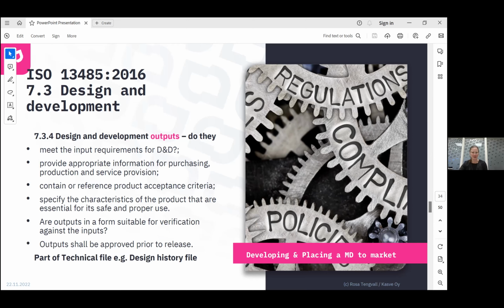You will have the outputs, again reviewing what we had as an input, and whether we met them when we had the outputs. Under medical device regulation, the output is not only the product output, it's also information for purchasing. If you need some licenses or some other hardware components for your device, you need to have that information as design output. You need to have production and service provision, instructions for use, training materials, etc., etc.